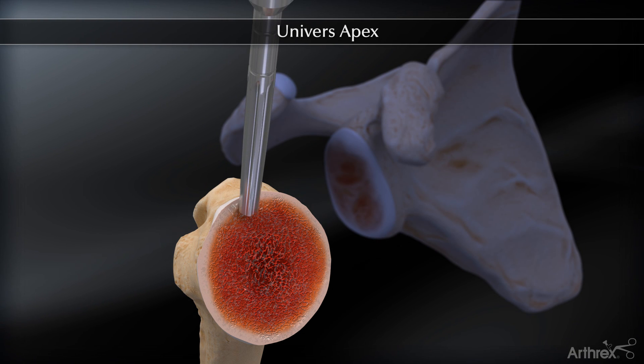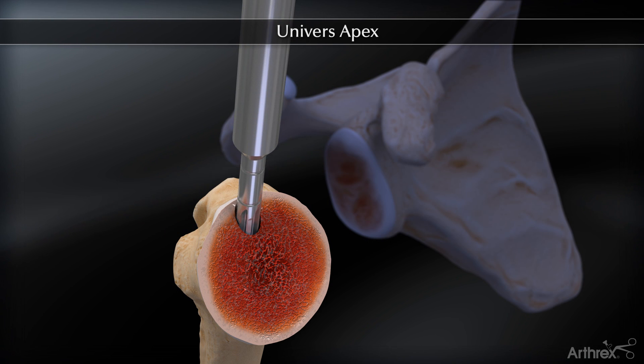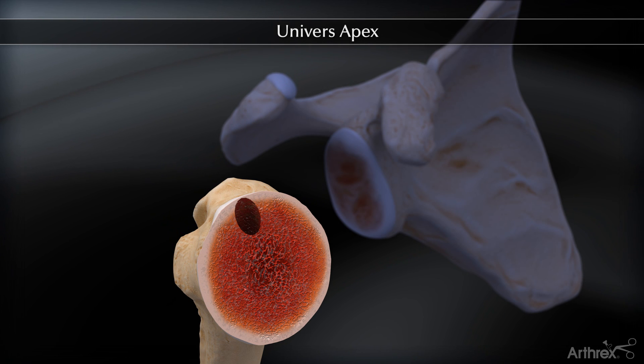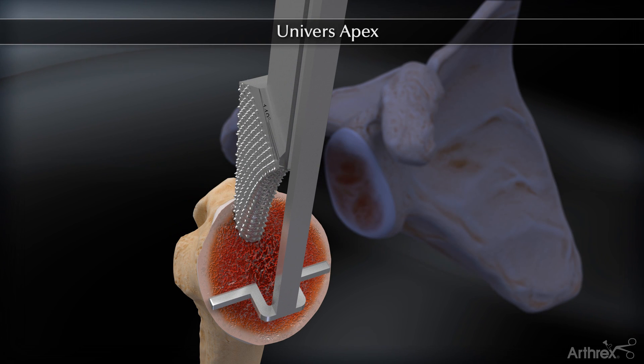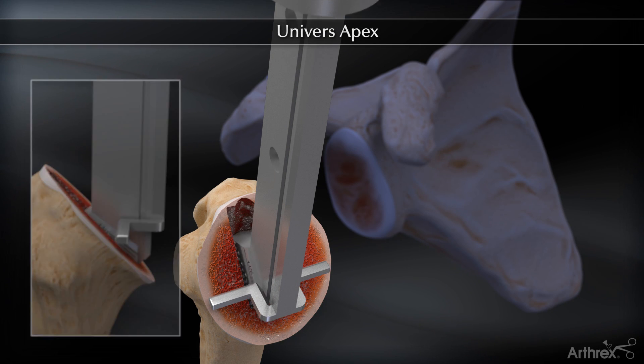The Univers Apex instrument set contains reamers and broaches designed to prepare the intramedullary canal to match the stem's smaller footprint, minimizing bone removal. The initial broach has an attachable version guide for proper broach orientation relative to the osteotomy.